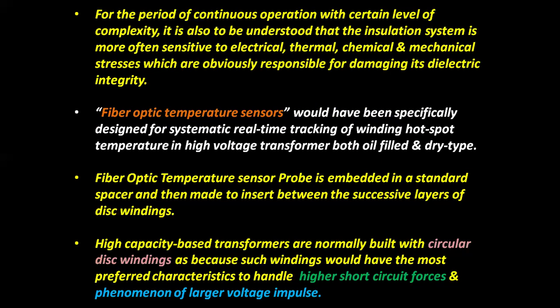Fiber optic temperature sensors are specifically designed for systematic real-time tracking of winding hotspot temperature in high voltage transformers, both oil filled and dry type. The fiber optic temperature sensor probe is embedded in a standard spacer and then inserted between the successive layers of disk windings. High capacity transformers are normally built with circular disk windings because such windings have the most preferred characteristics to handle higher short circuit forces and larger voltage impulse phenomena.